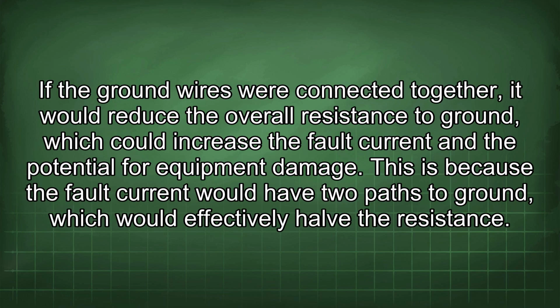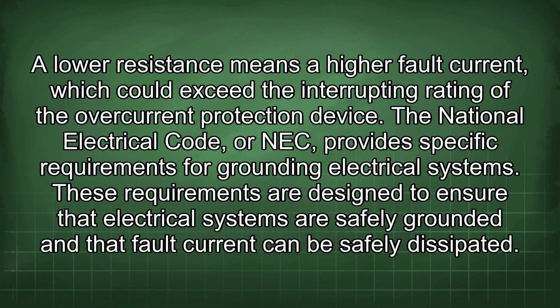If the ground wires were connected together, it would reduce the overall resistance to ground, which could increase the fault current and the potential for equipment damage. This is because the fault current would have two paths to ground, which would effectively halve the resistance. A lower resistance means a high fault current, which could exceed the interrupting rating of the overcurrent protection device.